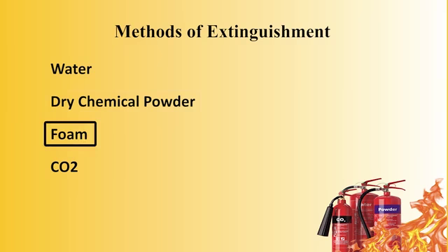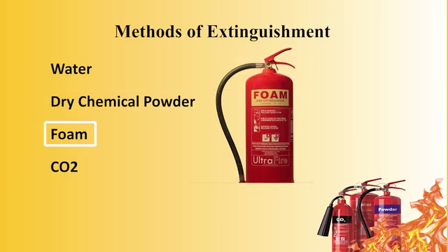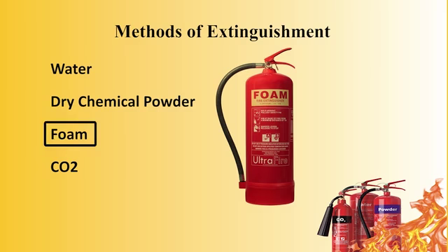And third one is foam. Foams are preparations of foam. Previously it was made by chemical reaction, this chemical reaction of aluminum sulfate and sodium bicarbonate. But nowadays mechanical foams are already invented, named as AFFF, aqueous film forming foam.